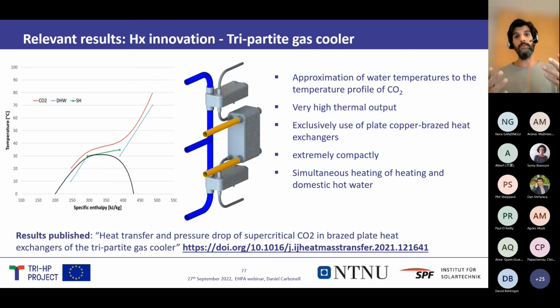When we work with CO2 in a transcritical cycle, when we reject heat, in the typical condenser, we have a gas cooler, so CO2 is not condensing. It's in a gas state, which means it has a very large temperature difference. As you can see in the red line here, it goes from 70, 80, down to 20. And this is very good for domestic hot water, but it's not good for space heating because we need a small delta T. Now, what NTNU has developed is what is called a tripartite gas cooler.